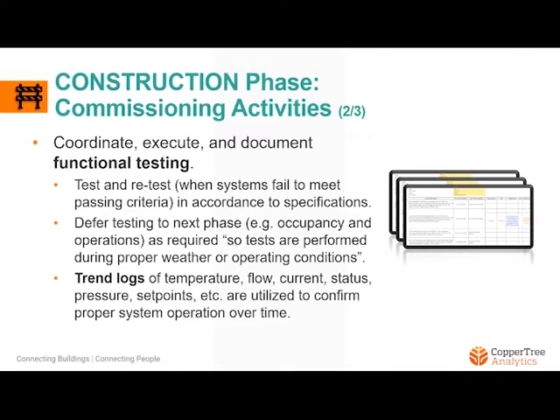The coordination, execution, and documentation of functional testing represents the bulk of the activities in this phase. This includes testing and retesting in accordance with specifications, deferring testing to the next phase as required so that tests are performed during proper weather or operating conditions, and once again, trend logs, which are essential in confirming proper system operation. These trend logs typically include temperature, flow, current, status, pressure, set points, etc., which are all utilized to confirm proper system operation over time.